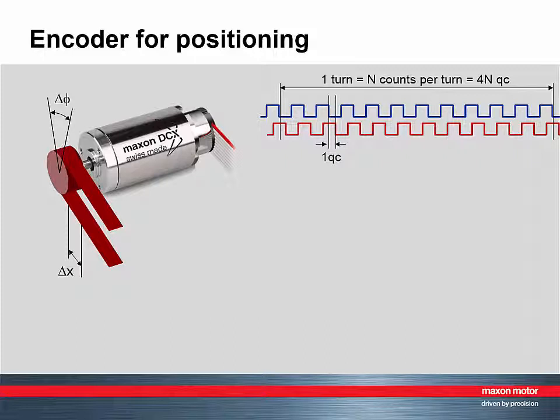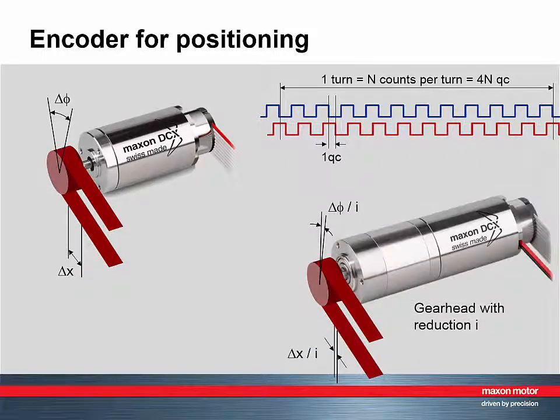an angular accuracy of one degree requires an encoder resolution of at least 360 states per turn or 90 counts per turn. Observe, encoders are mounted on the motor. Any gear head reduction increases the resolution at the load by the reduction ratio of the gear head.